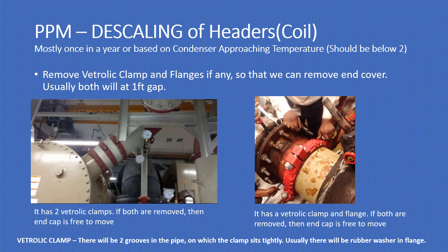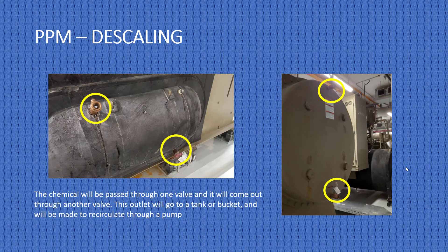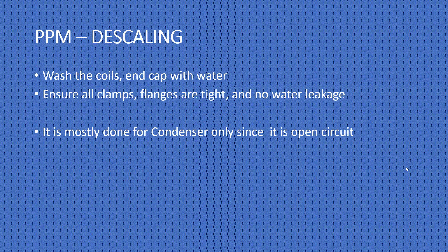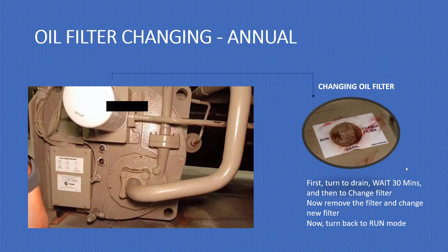For PPM descaling of headers — mostly once a year or based on condenser approach temperature — do descaling only if required. Remove the Victaulic clamps and flanges so the end cap is free to move. There will be two grooves in the pipe on which the clamp sits tightly; usually there is a rubber washer in the flange. For the de-scaling setup, a chemical is passed through one valve and comes out through another — this outlet goes to a tank and is recirculated using a pump. After descaling, remove the end cover, wash the water box coils and end cap with water, and ensure all clamps and flanges are tight with no water leakage. Descaling is mostly done for the condenser only, since it is an open circuit.